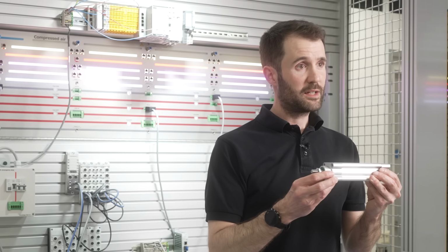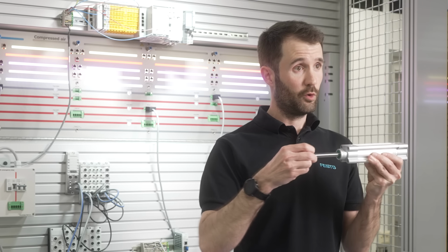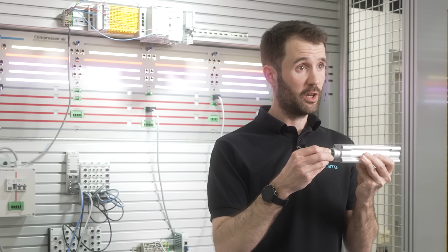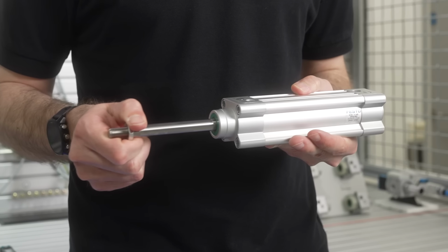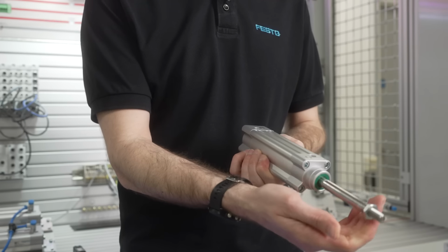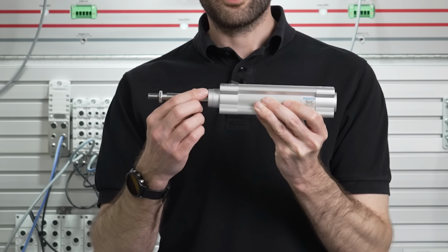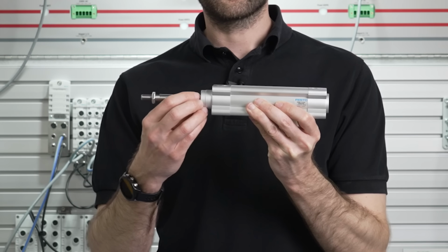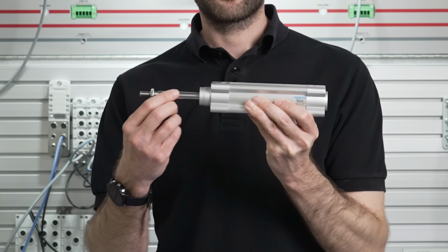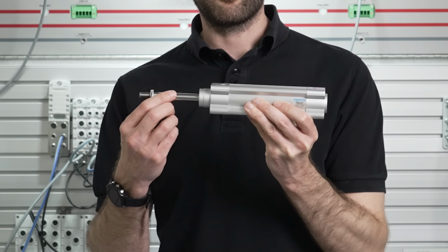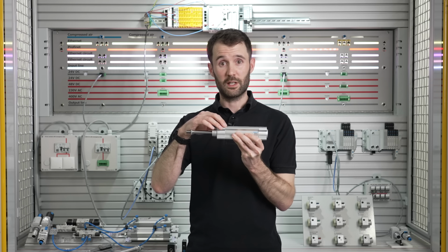So if I take this pneumatic cylinder here, typically we would have two types of motion, the forward motion and then the return motion. Now typically what might be happening here is you have a front nose seal, and on this front nose seal, because there could be side loads on the piston rod, this front nose seal can become loose and then start to leak. We may also see things like spotting corrosion along the side of the piston rod itself, which may impact environmental conditions going into the actual cylinder itself.